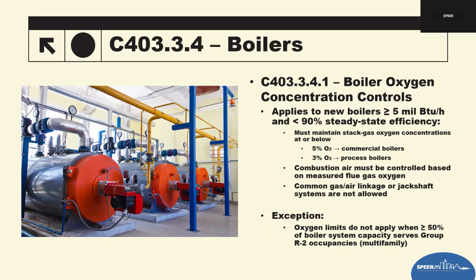There is an exception though in group R2. The only one exception, it says if 50% or more of the boiler system capacity serves group R2 residential occupancies like apartments, dorms, multifamily, these oxygen limits do not apply.